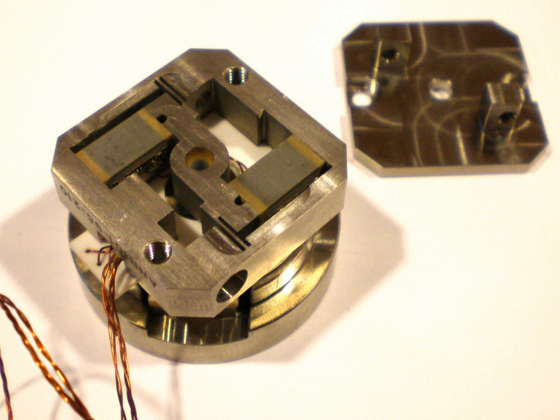Regardless of locking type, stepping type piezoelectric motors, linear and rotary, use the same mechanism to create movement. First, one group of locking crystals is activated to lock one side and unlock the other side of the sandwich of piezo crystals.